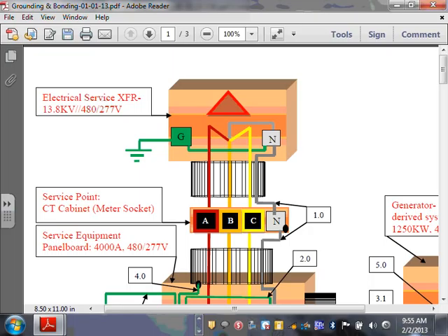As a matter of fact, just to go a little bit higher, if this transformer was 13.8 and the secondary of this transformer was 4160, high voltage, still the same. If that transformer was 13.8 coming to 4160, it's still the same, except when you go higher. Does anybody go higher than 600 volt? Do you guys size higher than 600 volt? The only difference in a higher than 600 volt system, if your system is grounded, is that you do not need to bring the neutral conductor into the service disconnect. So your neutral conductor here, if that was higher than 600 volt, does not need to enter the service unless you're using it. And typically for a building, we don't use the neutral. So when you take 4160 to a hospital, you really don't use a neutral, right?